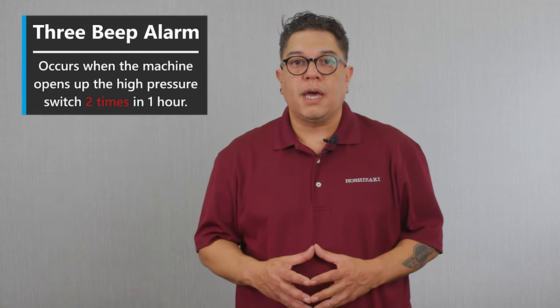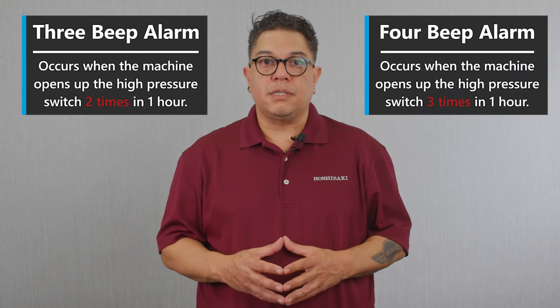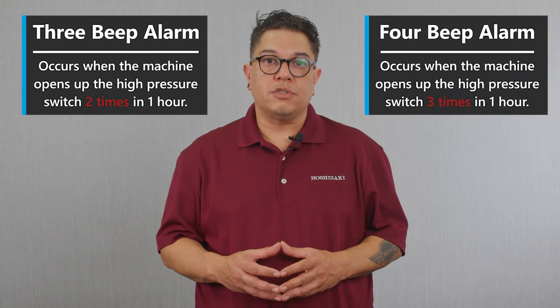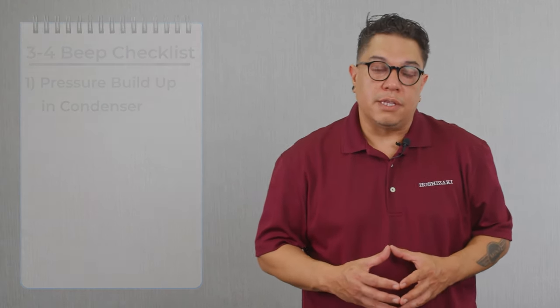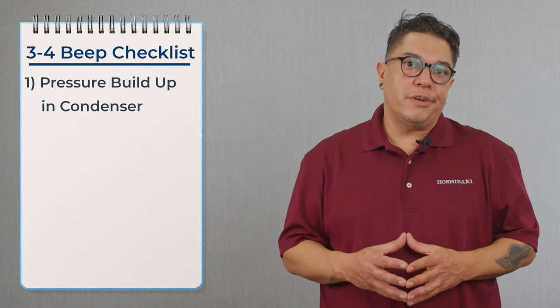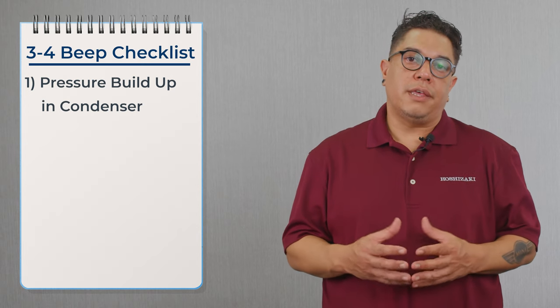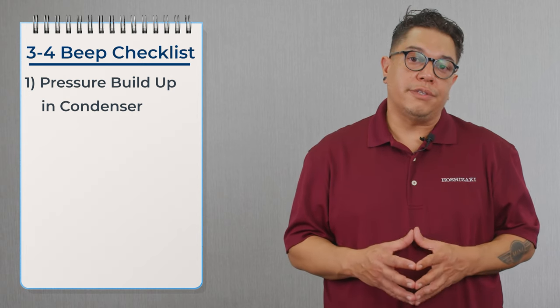Let's talk about the 3 and 4 beep alarm. The 3 beep is that the machine opened up the high pressure switch two times within one hour. The 4 beep is the same — the machine opened up the high pressure switch three times within one hour. The things that could cause the high pressure switch to open is that the machine is building up pressure in the condenser.